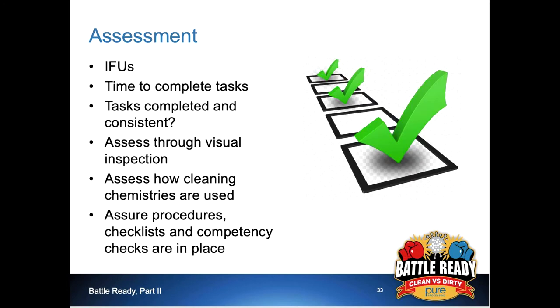Do your methods line up with the relevant IFU? How long is it taking each technician to clean complex devices? Are all steps performed completely and consistently?